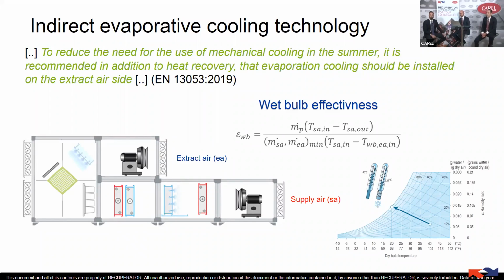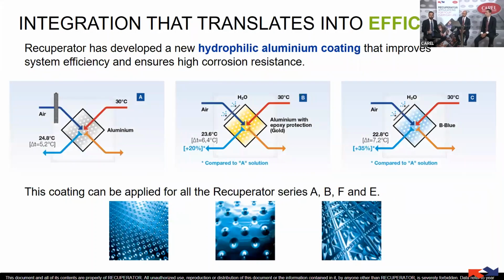Well said, Andrea, because we have seen that the keys are the integration between the humidifier, so CAREL, and the heat exchanger, so Recuperator, and the other important key is to wet the heat exchanger as much as possible. We can see now an example that supports what we have just stated. We have three different combinations of humidification system and plate heat exchanger. The first one, on the left, is a wet pad with a plate heat exchanger. So we humidify the air at the inlet of the heat exchanger, and then the heat exchanger is dry. Then we exchange the heat between the two airflows.